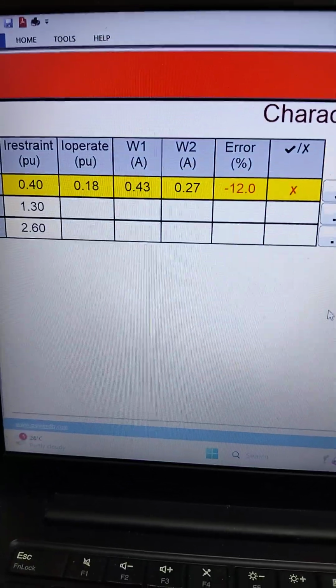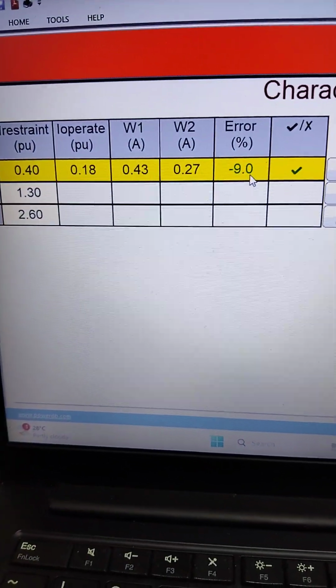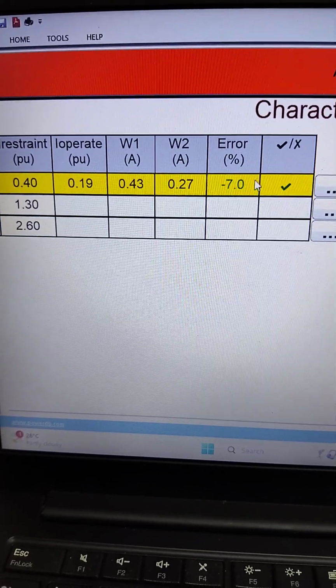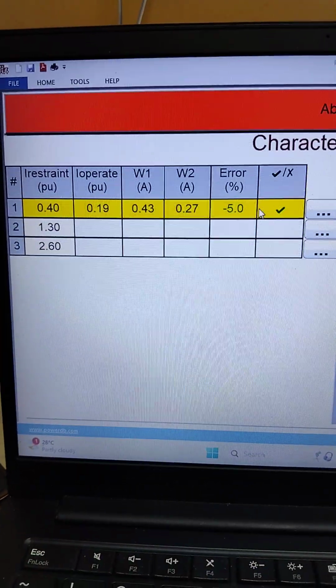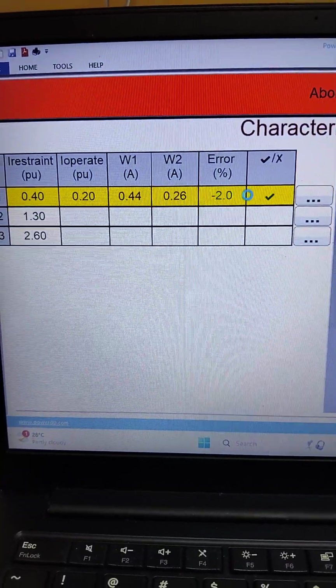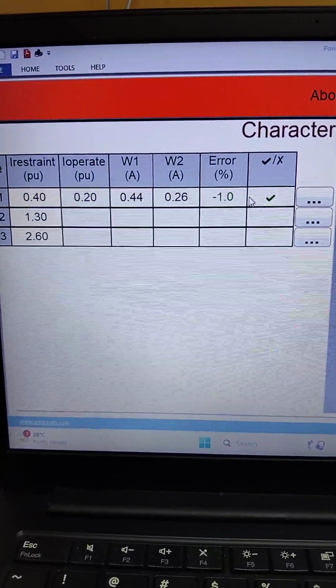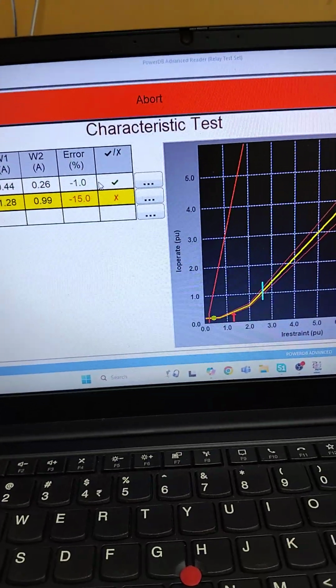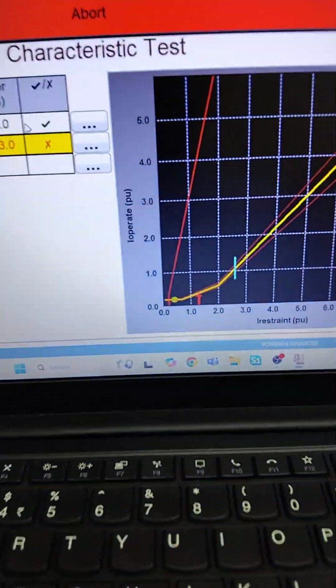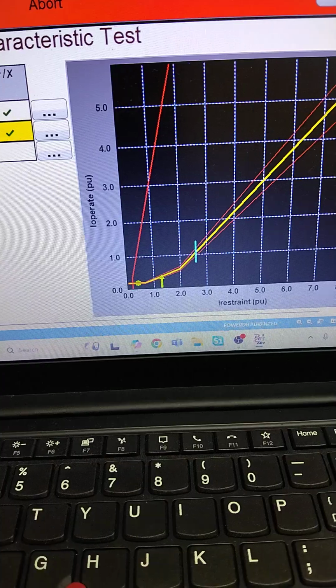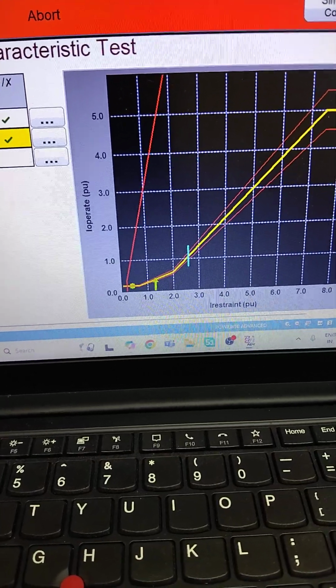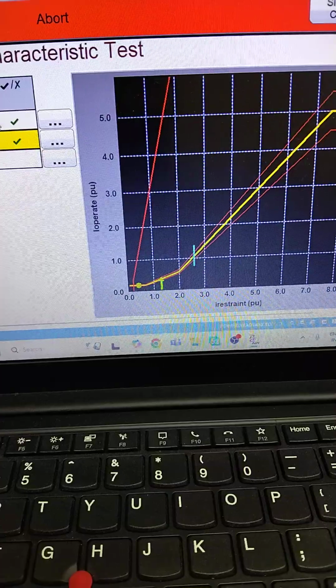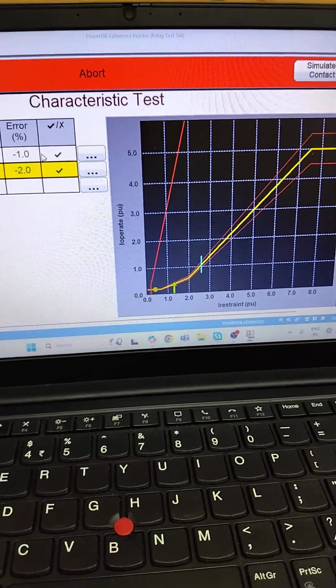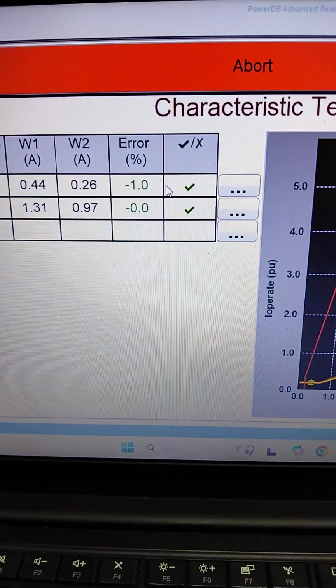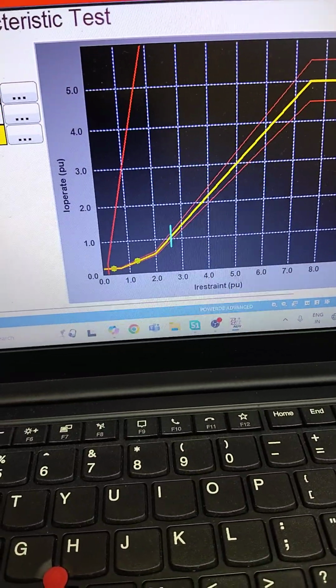So if it is exactly nearby, within your tolerance, that is 10%, you will get a green tick mark, so that means your test case has been passed. If you want to further narrow down the boundary, you can change the threshold value to 2.5% as per IEC. So now you can see the first case is passed, only 1% error is there. Now again it's within the threshold, but still we have not received a trip, so we are waiting for it. So now this is again the zero in slope number 1, the K1 section.